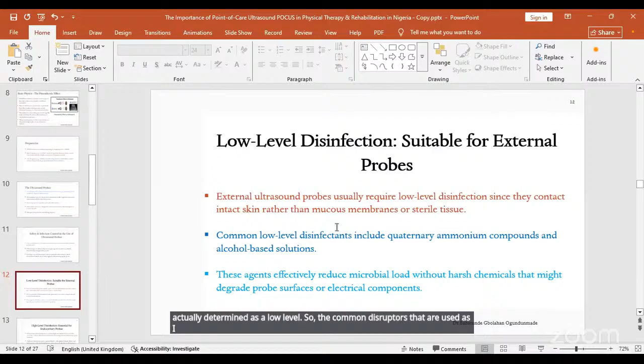But there is high-level disinfection, which is for the endocavitary probe. As you have seen in the slides I gave before, the endocavitary probe actually enters mucous areas like the vaginal area and the rectal area. So it contacts mucous surfaces, and there is more likely to be an issue of infection there. So it necessitates what we call high-level disinfection, because of the contact they have with the mucous membrane. Those high-level disinfectants are things like glutaraldehyde, ortho-phthalaldehyde (OPA), and also hydrogen peroxide. They are solutions that can be used to clean.